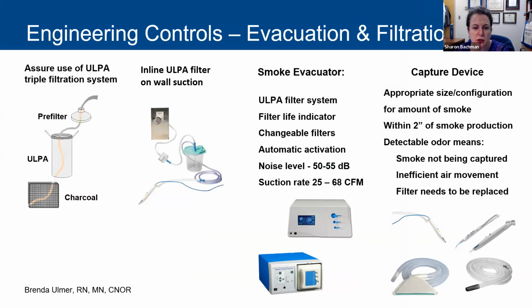Some of the engineering controls, some of the things that are relatively easy to do, are a lot of the different filters available. That ULPA filter, which can filter out almost 100% of 0.12 microns, can be part of an inline canister. The true suction devices, the suction systems, do a better job than just attaching yourself to a wall suction. They get rid of the smoke a lot better, but you can still apply a filter to a regular inline suction. And then the capture devices. I don't know if anyone has had the Go Clear AORN initiative at their hospital, but ours has, and all of our electrosurgery pencils now have a suction attachment on them. We also have suction attachments on our insufflators so that we can capture particulate matter.